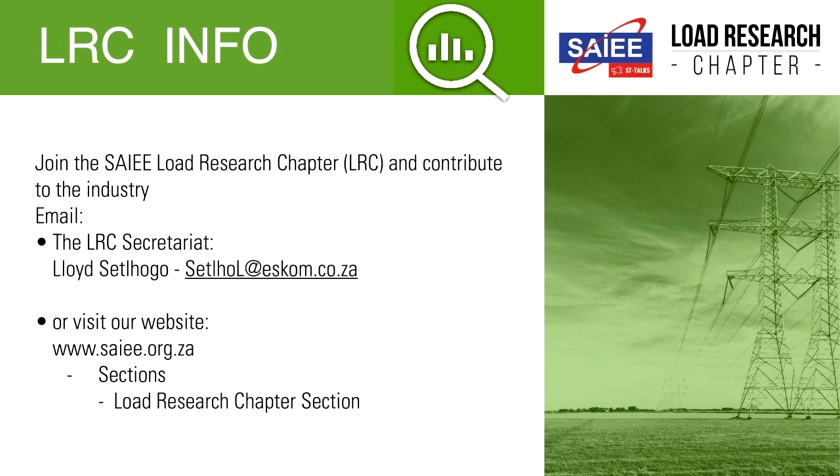Mainly when light fittings are imported from Europe, from your colder areas, that's where we're starting to pick up problems as well. The control gear, for instance, creates flickering and disturbances, because the environment where we install it in Africa is totally different to the European environment. That is where we're picking up problems. We need to get all our things in line and published out there so that we have something to work against.